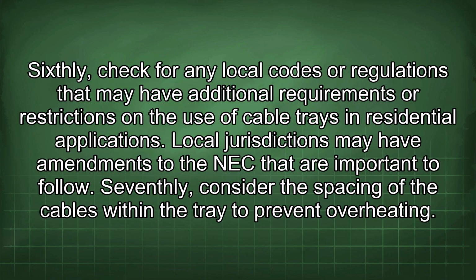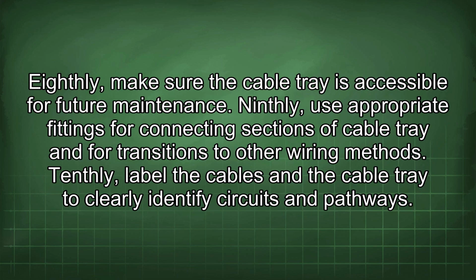Sixthly, check for any local codes or regulations that may have additional requirements or restrictions on the use of cable trays in residential applications. Local jurisdictions may have amendments to the NEC that are important to follow. Seventhly, consider the spacing of the cables within the tray to prevent overheating. Eighthly, make sure the cable tray is accessible for future maintenance. Ninthly, use appropriate fittings for connecting sections of cable tray and for transitions to other wiring methods. Tenthly, label the cables and the cable tray to clearly identify circuits and pathways.